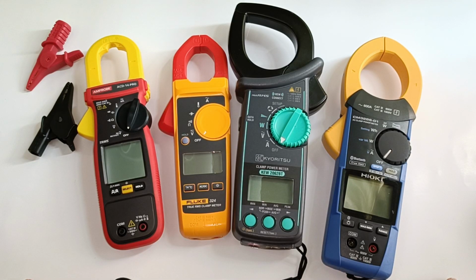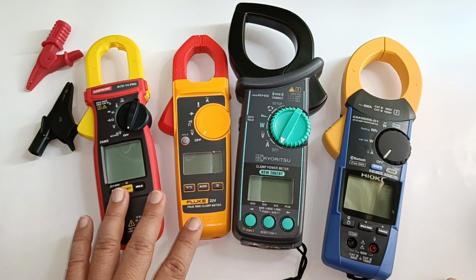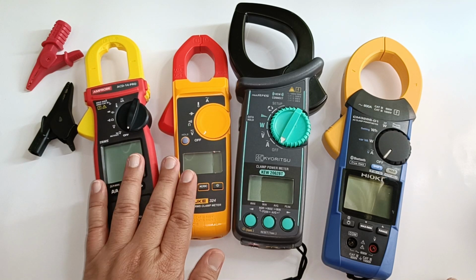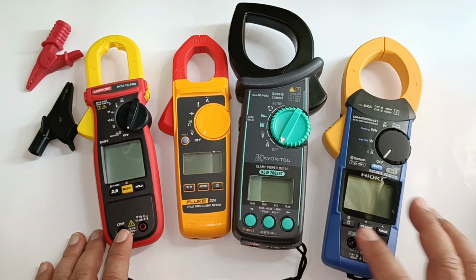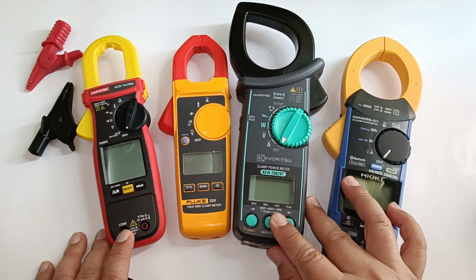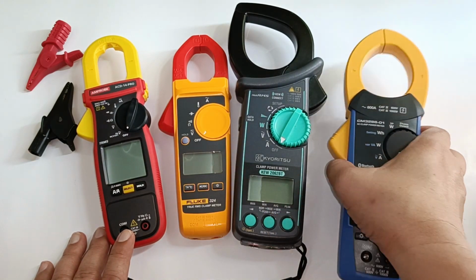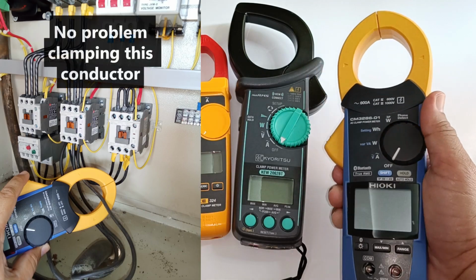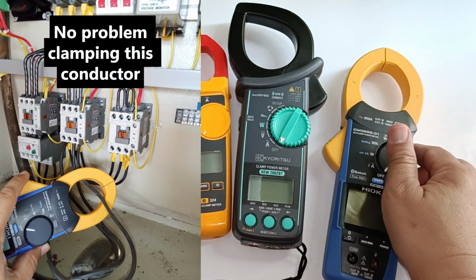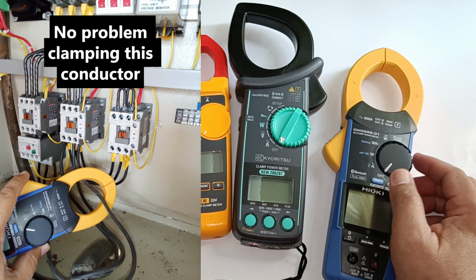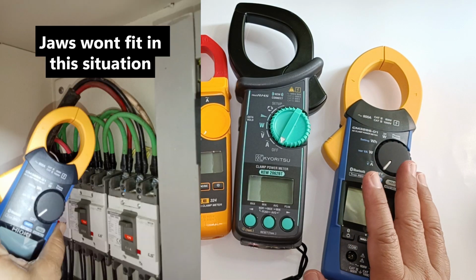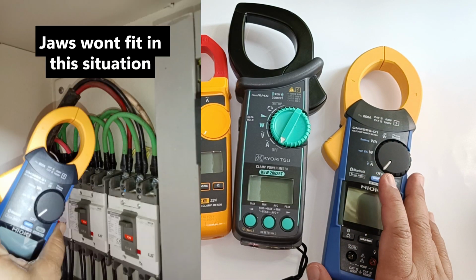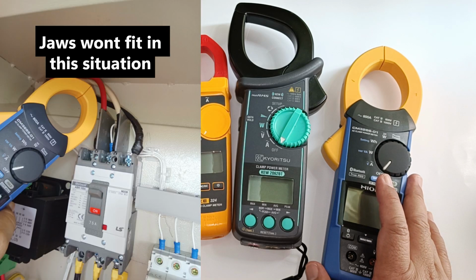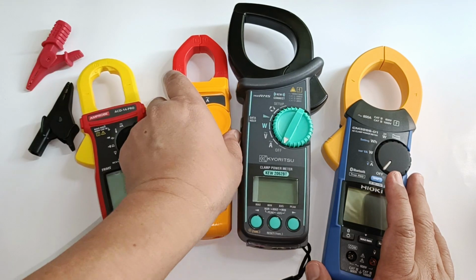One of the limitations of these clamp meters is in the inherent design of their jaws, and it applies not just for the standard clamp meters, but also for the specialized AC power clamp meters. While the jaws facilitate easy and safe measurement of current, the size of the jaws may not always allow it to work in tight and confined spaces. In conductors and cables installed very close to each other, the jaws may not be able to fit.